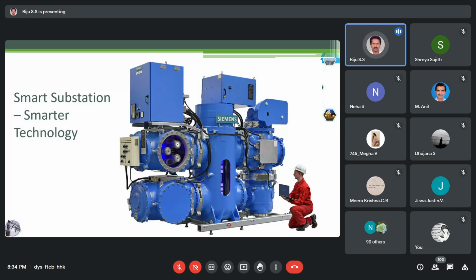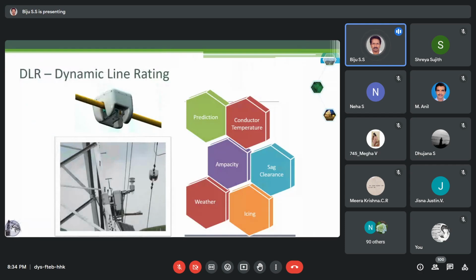It is the latest in GIS. It's available for CTs also nowadays, and in AIS also it's going to come up. I think it's already there. Another technology is optimization of lines, dynamic line rating, wherein the thermal loading of any line is determined by the design parameters based on ambient temperature, like maximum permissible conductor temperature, wind speed, solar radiation, absorption coefficient, humidity coefficient, sag, etc. By remotely monitoring all these things, the system can determine what should be the loading of my line at any particular point of time, depending upon the ambient conditions and the sag of the conductor.